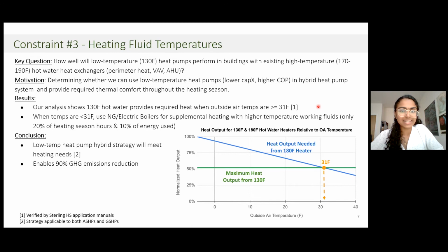And so what this means is that for that heat pump component of that hybrid system, we can actually use a low temperature heat pump instead of a high temperature heat pump. And we can use a natural gas boiler or an electric boiler for supplemental heat on the coldest days. And this will actually provide us with higher temperature heating fluid in addition to decreasing the peak electrical demand at that point.